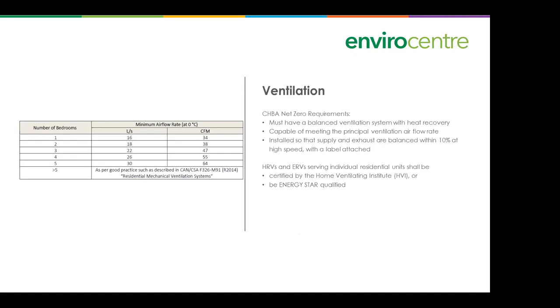Ventilation. With all this air sealing, we need to provide adequate ventilation. Under the CHBA program, you have to have balanced ventilation with heat recovery. It has to be capable of meeting the principal ventilation airflow rate and installed so that the supply and exhaust are balanced within 10% at high speed. There's a label attached for that. So that's a similar requirement to R2000.